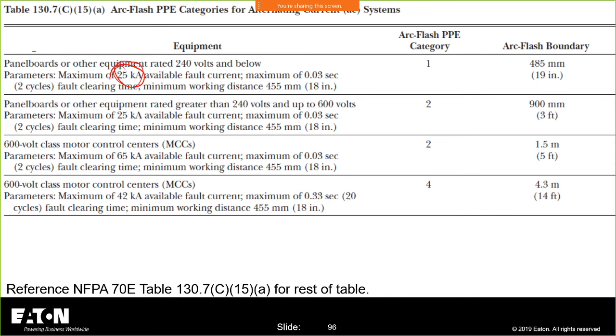Now, I have a fundamental issue with this, not that the table method's a bad thing or anything like that, because I know, and what you'll learn if you come into breaker basics, the more current you give an overcurrent device, the better it works, especially with incident energy. The less current you give it, the longer clearing time you could have. So they put a maximum of 25,000 amps, but if I'm downstream of a fusible switch or downstream of a 65K breaker, I feed that device current, I'm going to clear faster and I'm going to reduce my incident energy.